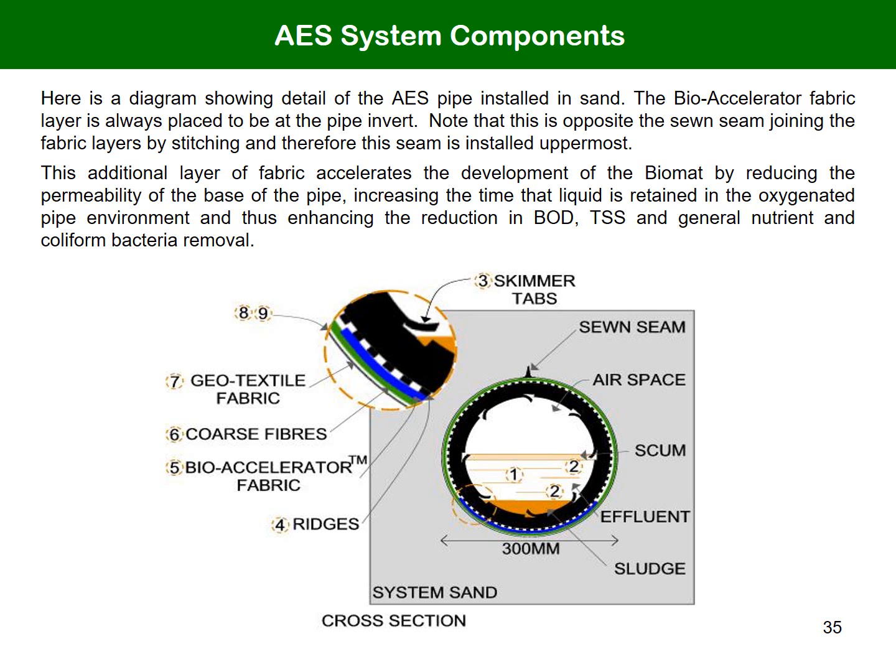Here is a cross-section of the various layers making up the pipe in place. The bioaccelerator pad is coloured blue in this representation. The other key component of the AES system is that the pipes are installed in clean coarse sand. This second process mirrors that of a sand filter, which has been in use in water and wastewater processing for a very long time.